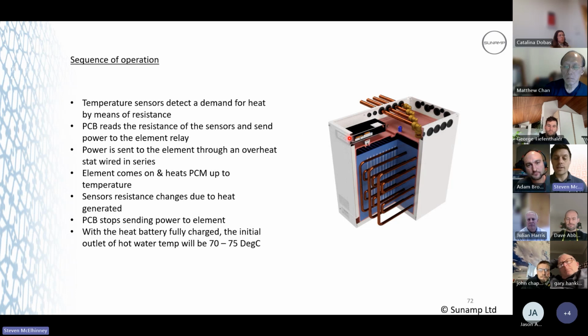That power is then sent down to our element via an overheat thermostat, which is wired in series. Element comes on and heats the PCM up to temperature. The sensor resistance changes due to the heat being generated, so that resistance then lowers. And then once it's up to temperature, the PCB stops sending power to the element, it de-energizes relay 1, basically. And with the heat battery fully charged, the initial outlet hot water temperature will be between 70 and 75 degrees. So that's why you need that blending valve.